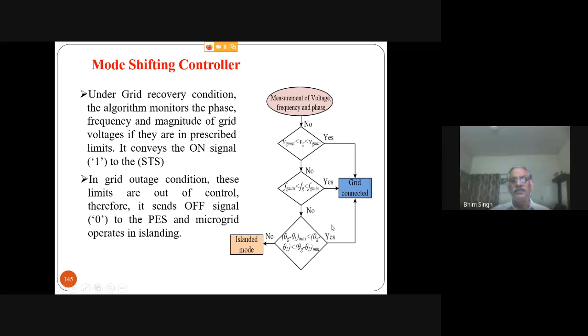Of course, we do the MPPT, and you will see, interestingly, that the standard normally says it should take around 10 cycles, but we are able to get even 2 to 3 cycles. You see the grid appears here and we are closing the switch here. So hardly after a couple of cycles, the load is not disturbed, because you can see the load voltage remains there. The load voltage is your yellow trace, so it remains there. Grid voltage coming or going is a different issue, but synchronization takes hardly a couple of cycles after the grid appears, while the standard says 10 cycles.